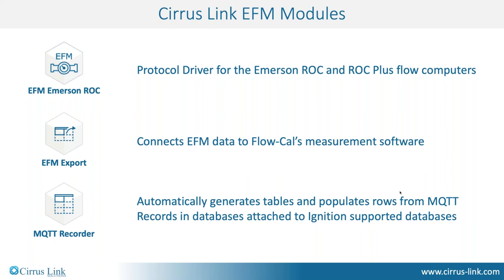The MQTT Recorder module automatically generates tables and populates rows from records published from edge applications, such as Emerson ROC driver event data. It includes security hash marks on record data so when published you have authentication and validation of that data. It automatically adds new columns when records contain new items, populates rows, and provides an audit check tool so you can validate that the record hasn't been modified or changed within Ignition. With that, I'll now pass on to Arlen to talk about MQTT.